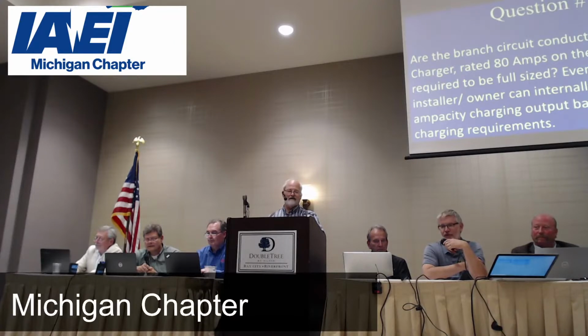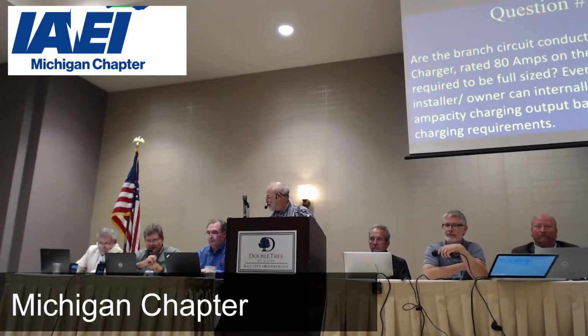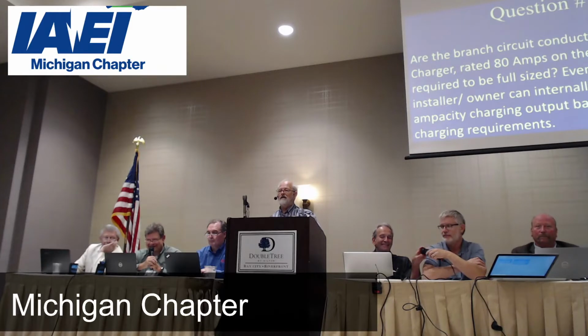And I would have to say that you have to remember there is a provision in the MRC, if you look in the first application, in the first part of that book, it says that anything not addressed in this book, you can fall back to the NEC. So if it's not specifically addressed, you can go back to whatever the National Electrical Code says. So 2017 say? I can't speak to that right now. I don't know. Yeah, the 2017 does not address being able to adjust the setting on the equipment. So that's where there's the advantage of adopting the 2020 NEC.